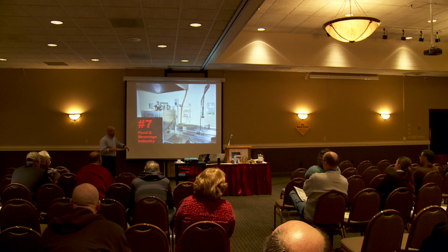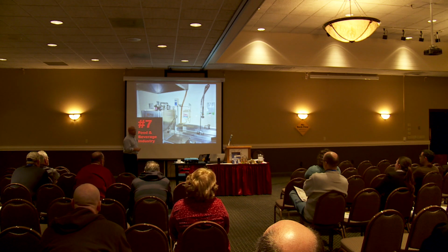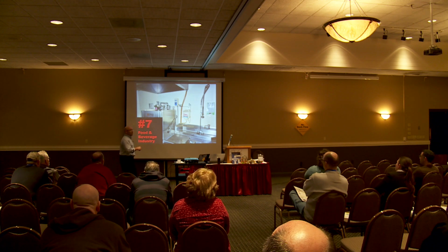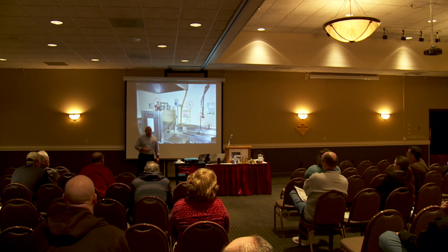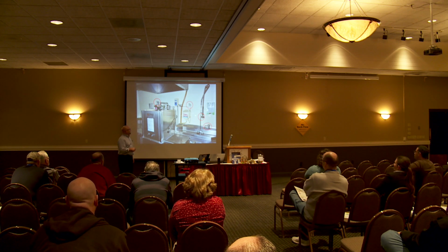Nancy, I saw you point over there. What'd you see? Where at? Good eye, Nancy, right here. That's a vacuum breaker. Oh, Nancy's pointing up where? Right here. Here's another vacuum breaker. Here they are. 4 of them. Air gap on the rinse.